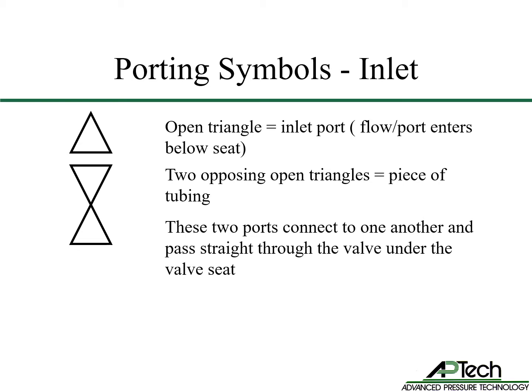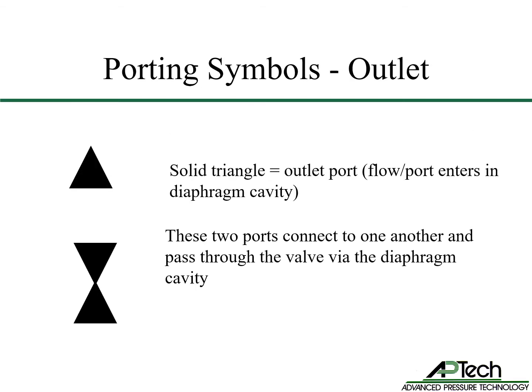Two opposing triangles represent two common ports connected below the valve seat. A solid triangle is an outlet port — this port is downstream of the seat. Two solid triangles represent two common ports downstream the seat passing through the diaphragm cavity.